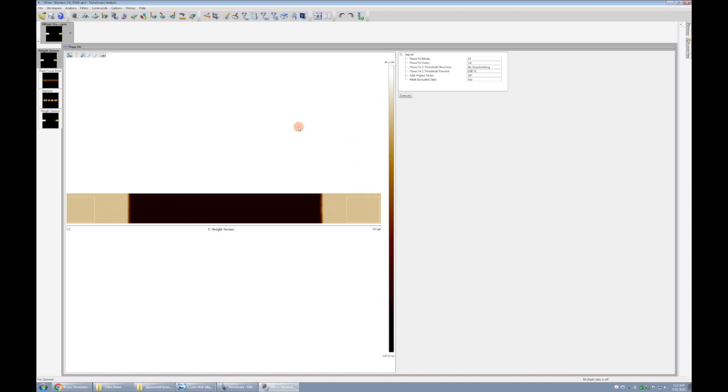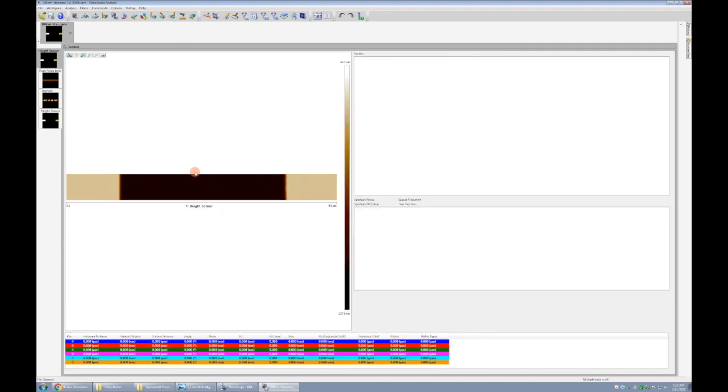So in our lab, some of the major analyses that we often do are things like section, and we can draw a line across that and then move these cursors, one on the top, one on the bottom, and then down here we can see a vertical distance of 179.34 nanometers. So again, this should be 180, so we're really close. We have a well-calibrated scanner.